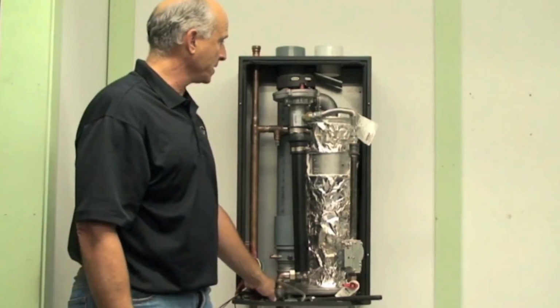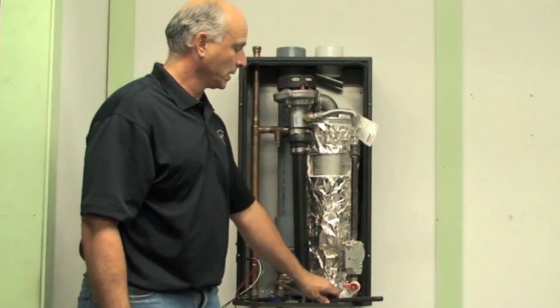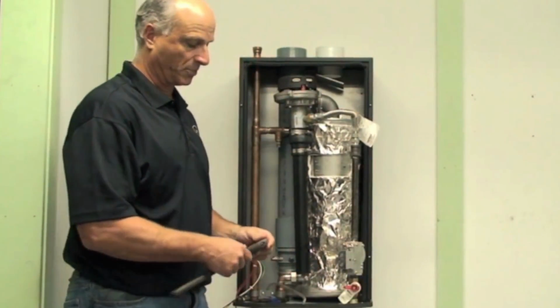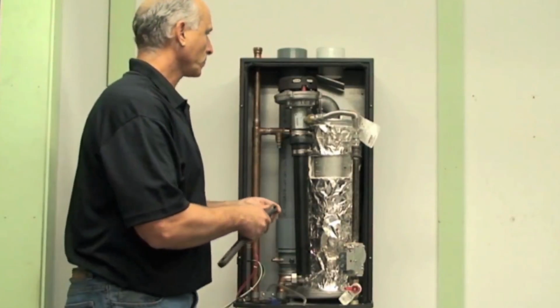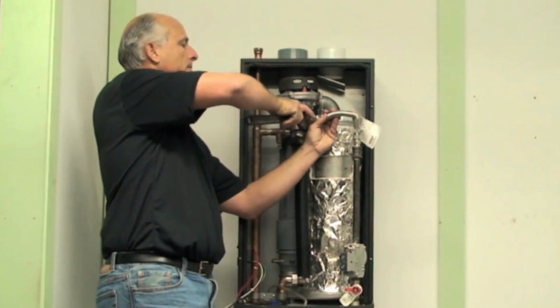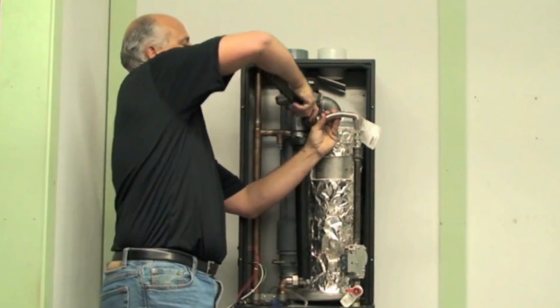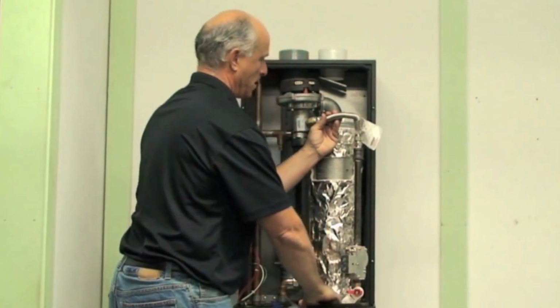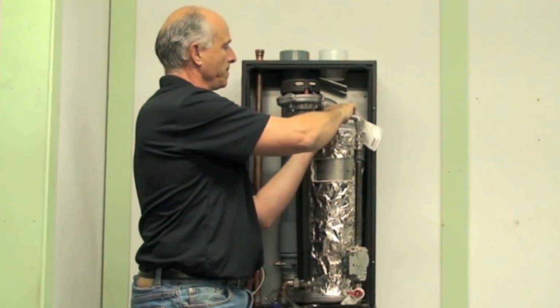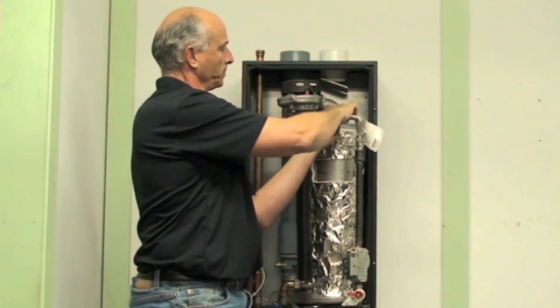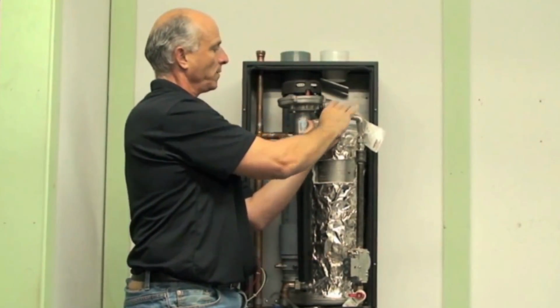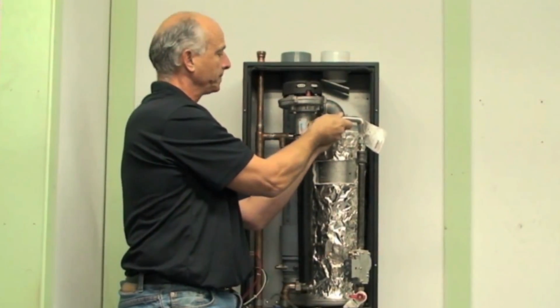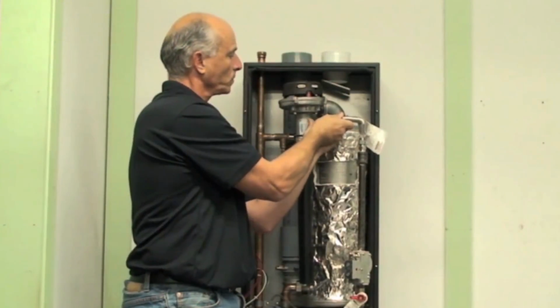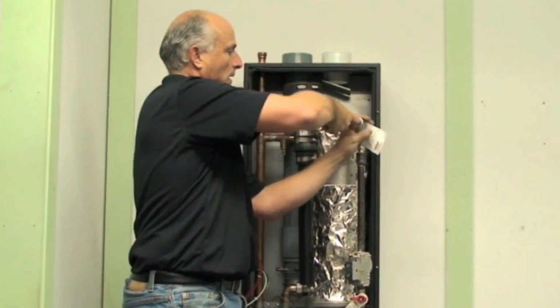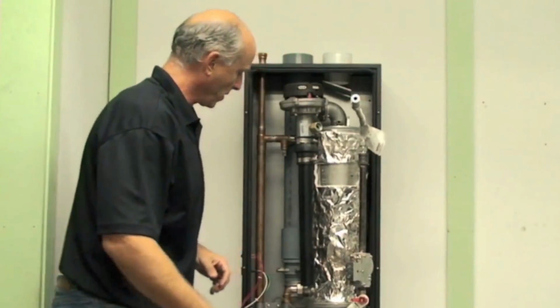Next, what I'm going to do is I'm going to take the fan assembly off. First thing is I'm going to take my adjustable wrench. I'm going to loosen the pipe here. Disconnect the unit. And the flexible gas line coming in. So get it out of the way.